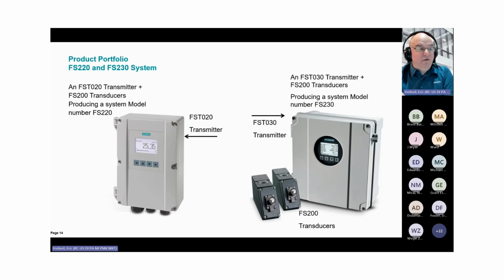So some of the hardware, as far as overall pictures and stuff, this is our FS220. This is a liquid flow meter only. It's primarily for the water and wastewater industry. It's a relatively cost-effective installation. It is not pricey at all. It's a single channel system, and we usually use these, as I said, in water and wastewater. We use it as a check meter in some chemical applications where they don't need approvals. But if you need approvals, you move over to the 030.